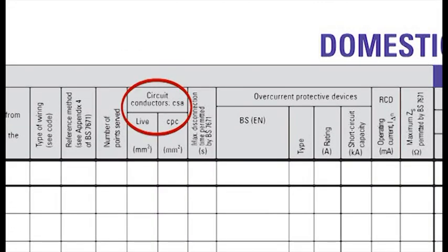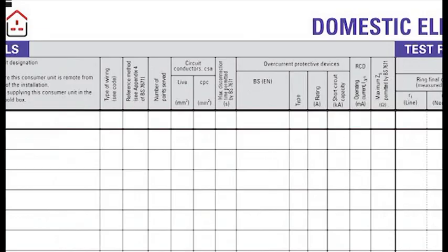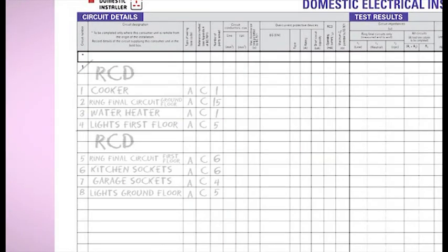Next, we have the cross-sectional area of live and CPC conductors. If you're using standard twin and CPC cables, you shouldn't have many issues here, as there are tables published for the complete range of conductors from 1 mm squared up to 16 mm squared.